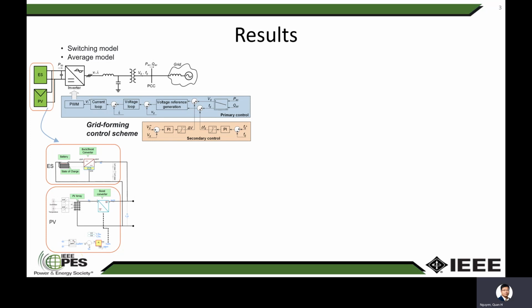So this is the grid forming control scheme that we developed for the plant inverter. It has a primary control loop and secondary control loops. The primary control loop includes the droop curve and the familiar voltage and frequency control loop, voltage and current control loops. And for the secondary control, it has PI controllers here to make sure that the voltage magnitude and the frequency at the point of common coupling are equal to the set points.